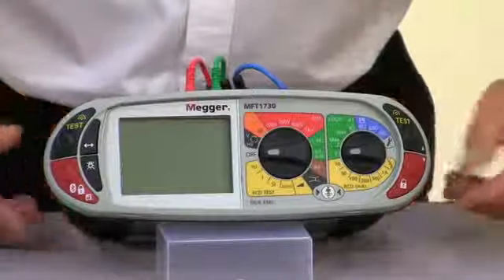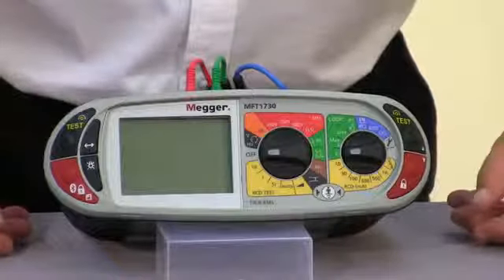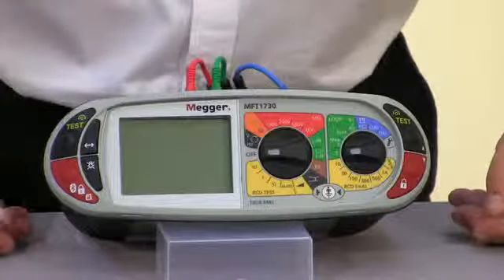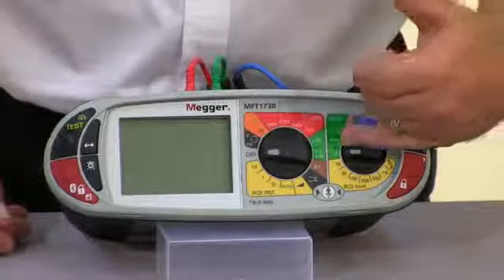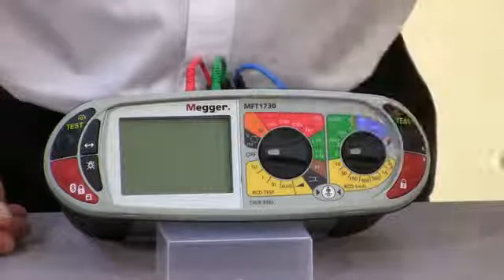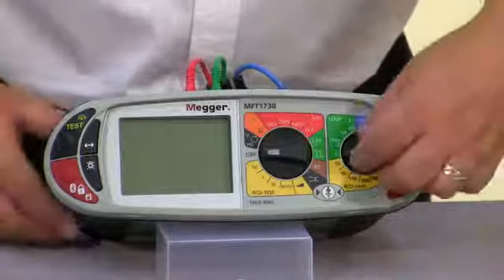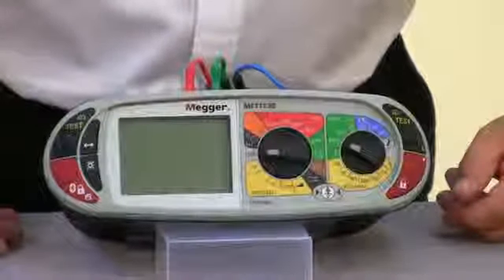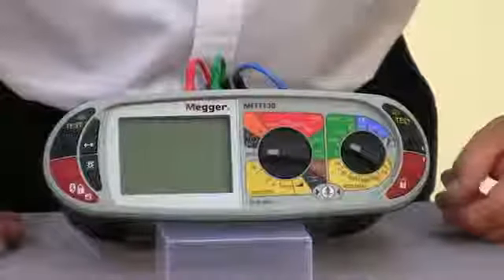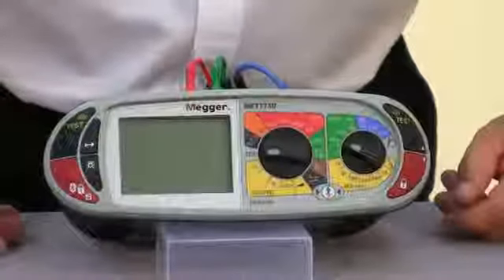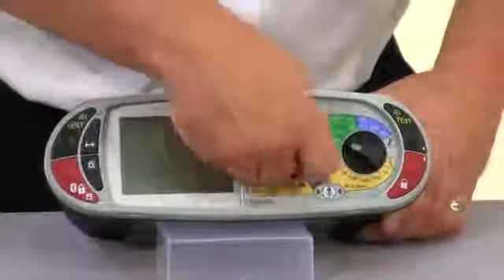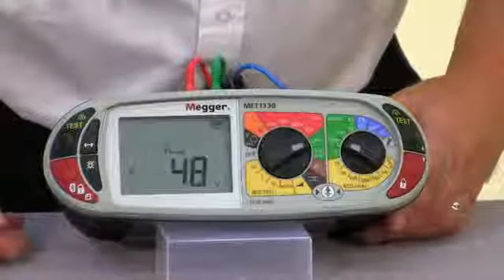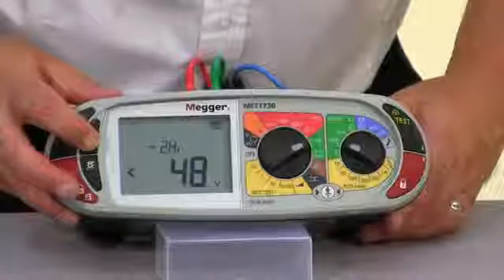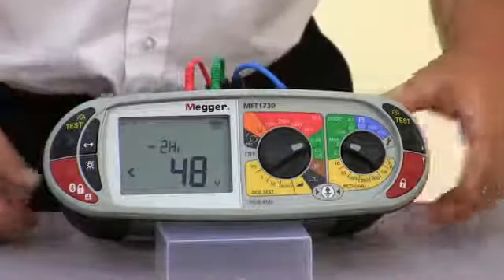Okay, so let's look at the other features that are available for loop impedance testing on the 1720 and the 1730. You'll see we have a Zmax, a reference and an R1, R2 facility. Selecting the Zmax first, this will allow us to carry out a sequence of tests whereby the highest reading is always returned on the upper of the two parameters on the display. So I'm just going to do a 2-wire high current test. So we're simulating testing on an unprotected circuit.